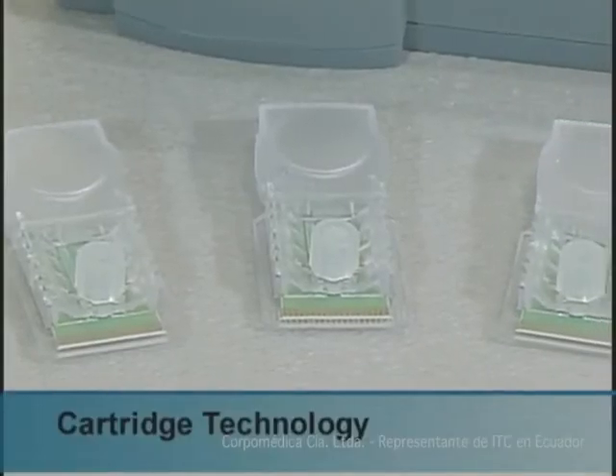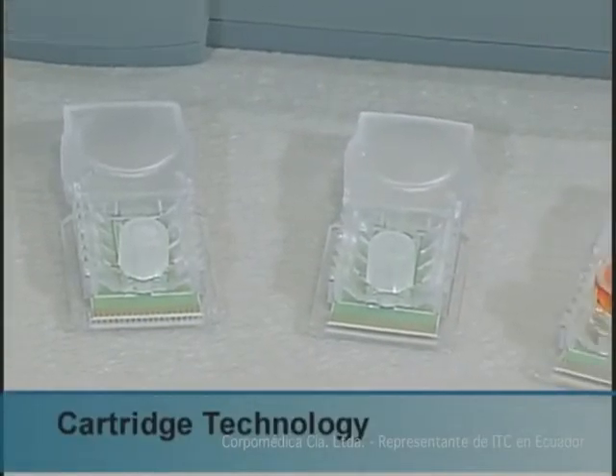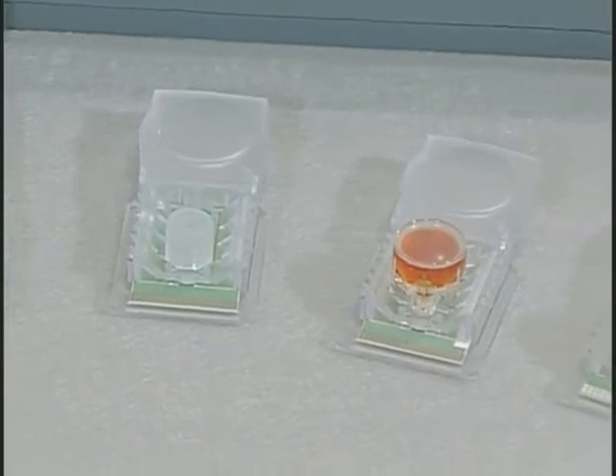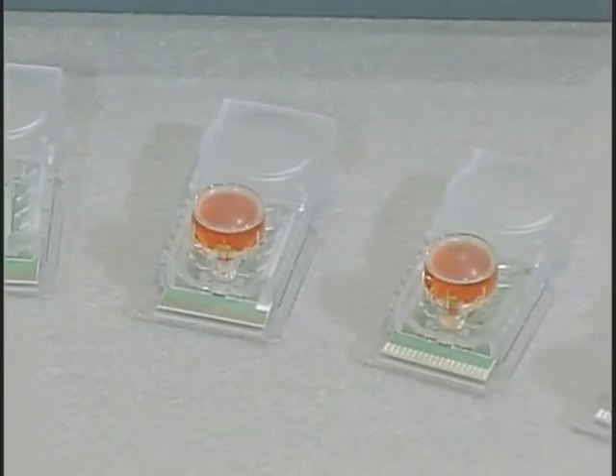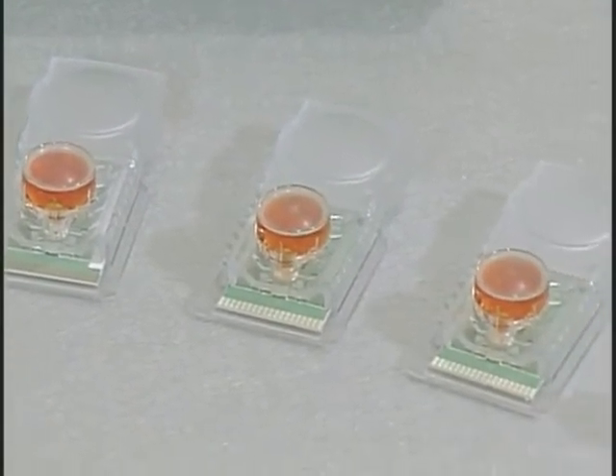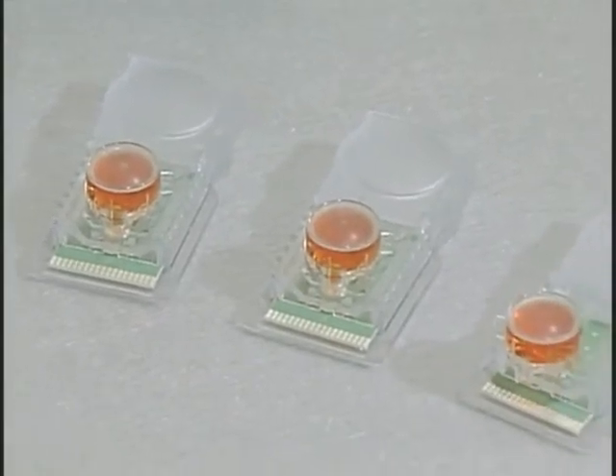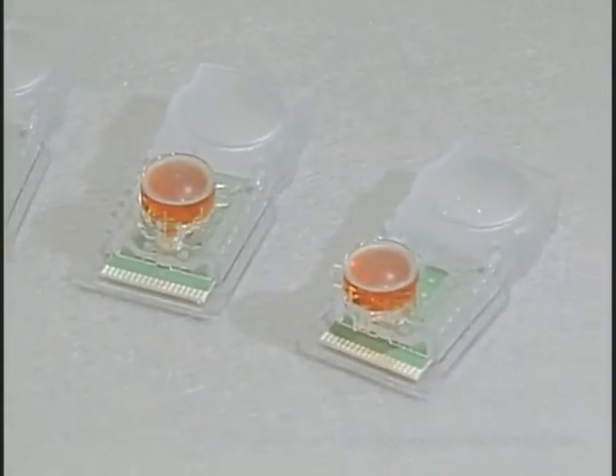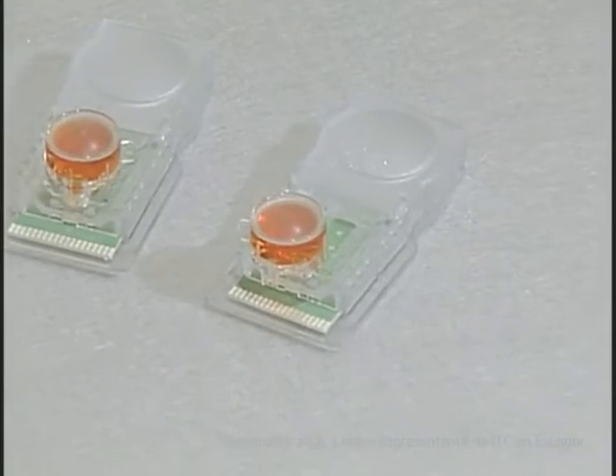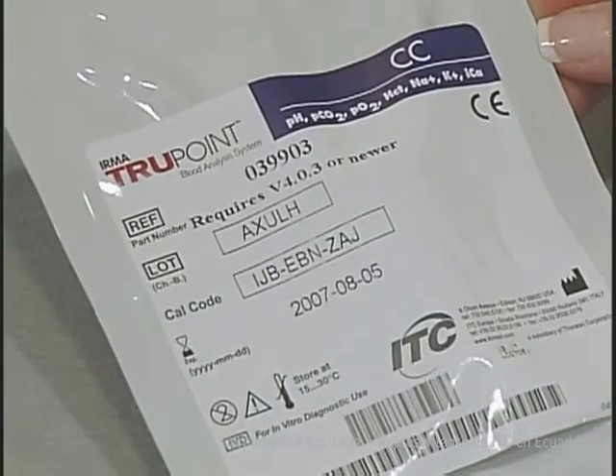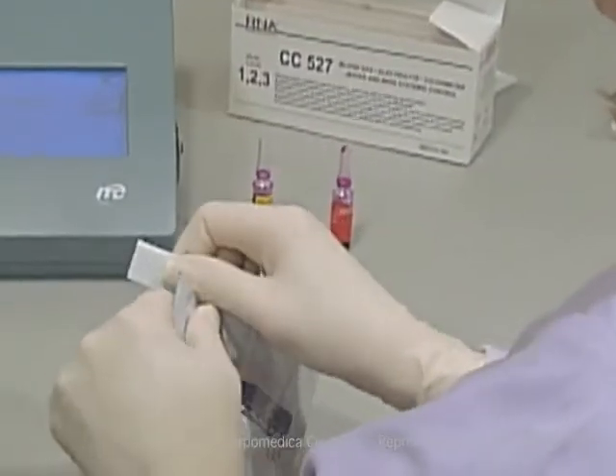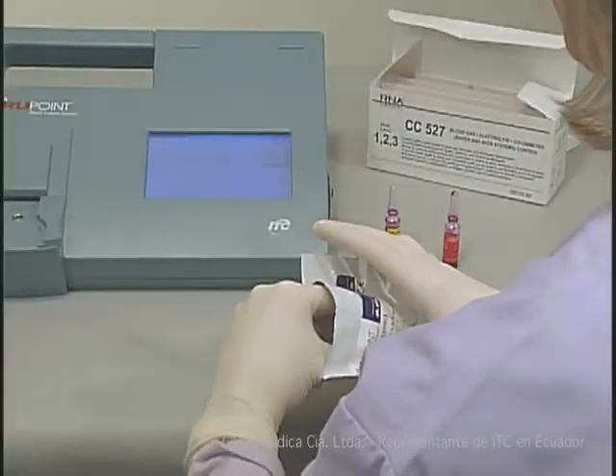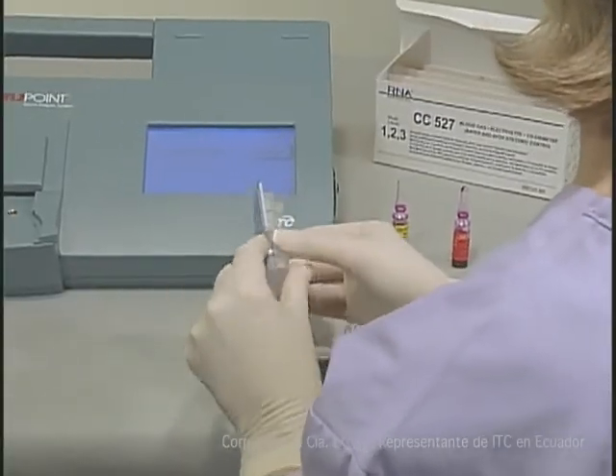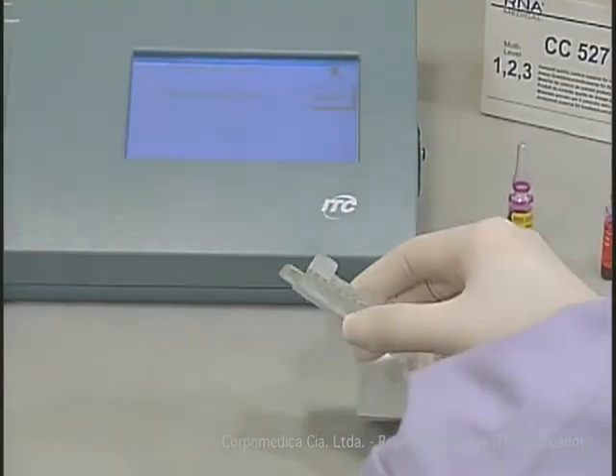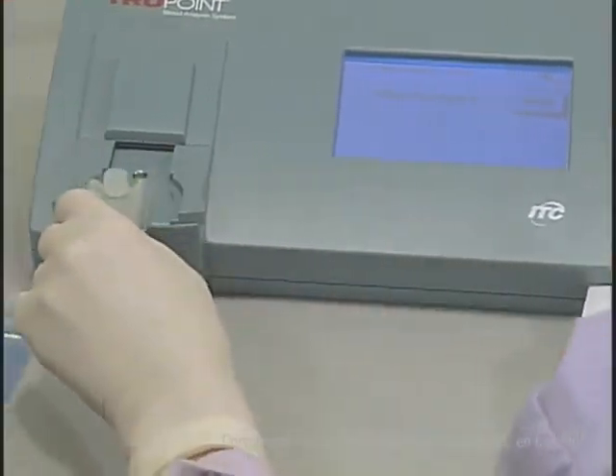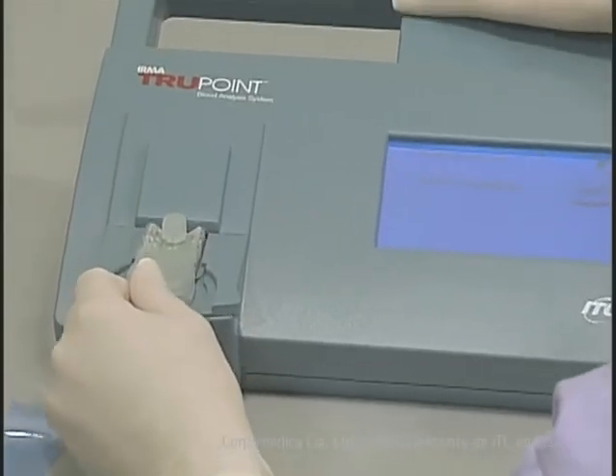The TruPoint cartridge utilizes a closed system technology that reduces biohazards. Each cartridge contains miniaturized electrochemical or enzymatic sensors and an onboard calibrant. With a wide operating range, the IRMA TruPoint can be used in cooler environments, such as the OR. Most IRMA TruPoint cartridges are stored at room temperature and are ready to use anywhere, anytime. By employing disposable sensors with a single-use cartridge, the IRMA TruPoint brings the laboratory to the bedside.